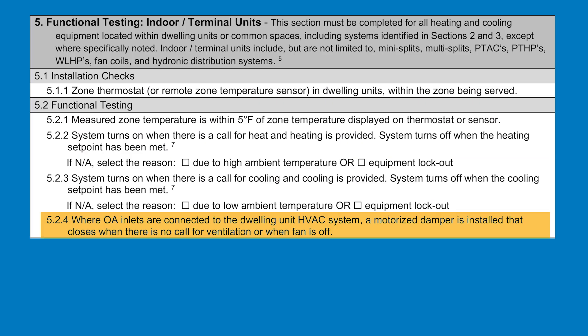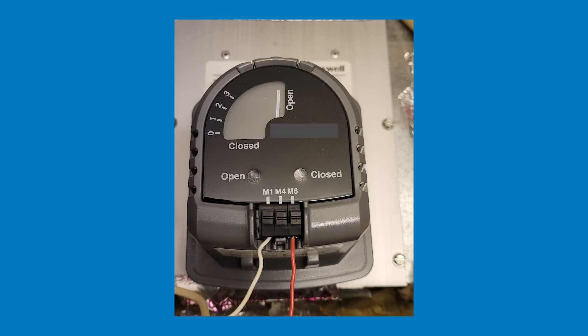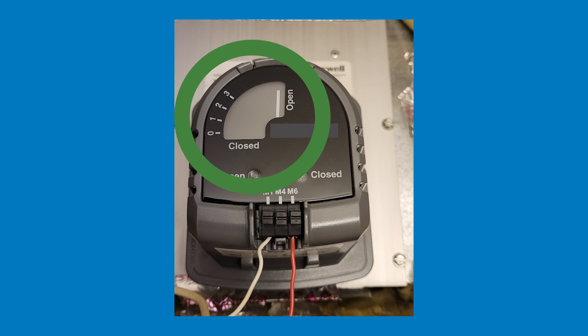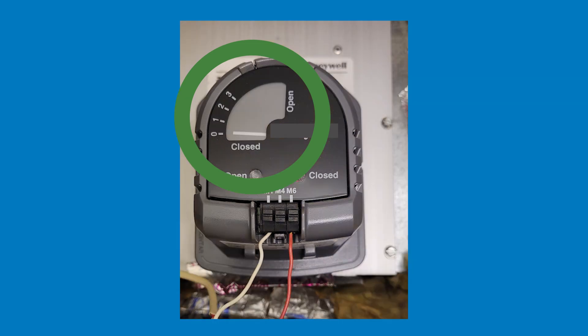Section 5.2.4 is applicable where an outdoor air inlet or duct is connected to the dwelling unit HVAC system. Confirm that a motorized damper is installed that closes when there is no call for ventilation or when the fan is off. Locate the outdoor air damper and confirm you understand where the indicator is for the open and closed positions, then confirm it is open when there is a call for outdoor air and closes when there is no call for outdoor air or when the fan is off.